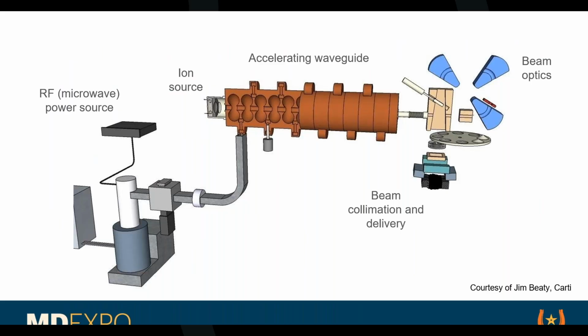The klystron needs a high voltage pulse, maybe about 100 kV, 100 kilovolts. So it's a lot of high voltage. Once the microwaves get into the accelerator, we have an ion source for the electrons. Usually the waveguide, because it's longer, we want higher energy. It's pointing horizontally. So the patient is going to be down over here, the accelerator is going to be over here, and we've got to get the beam pointed at the patient.